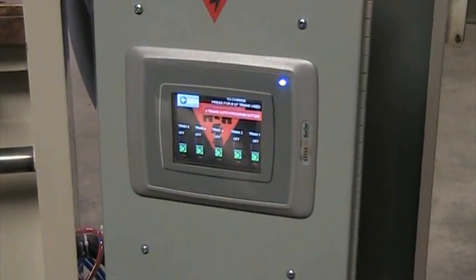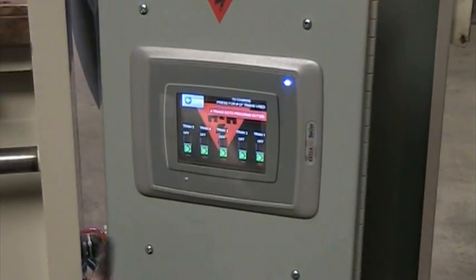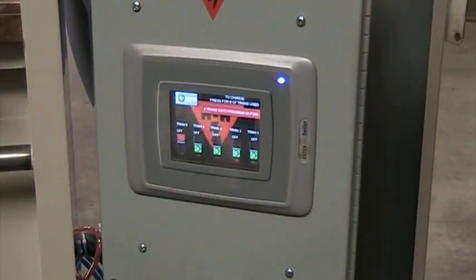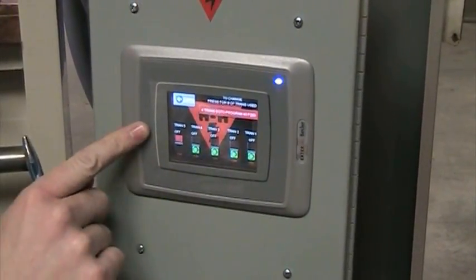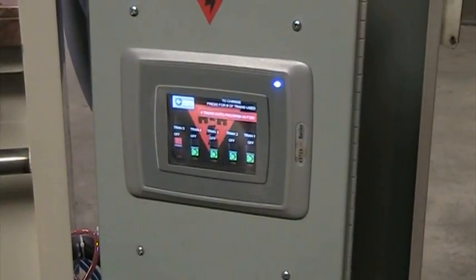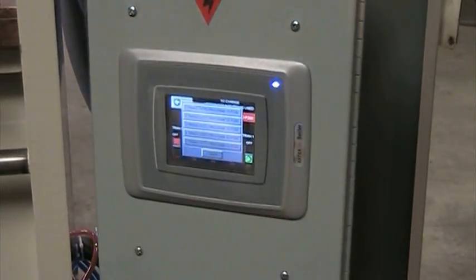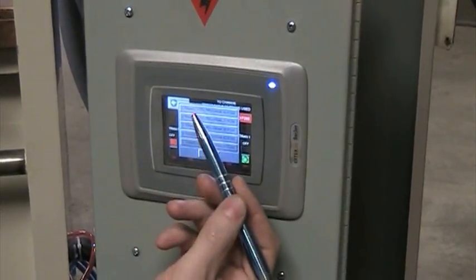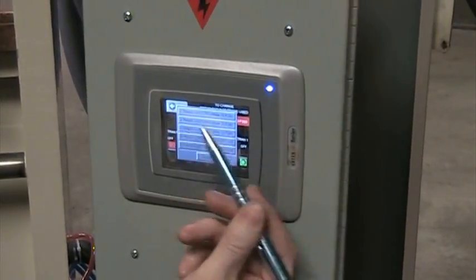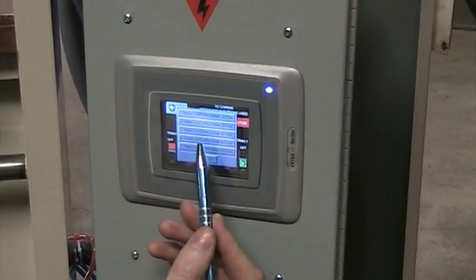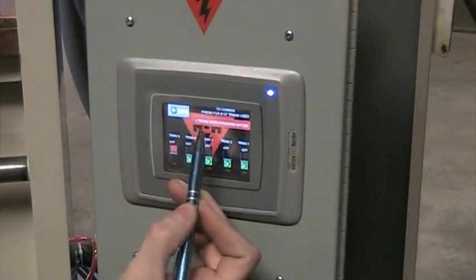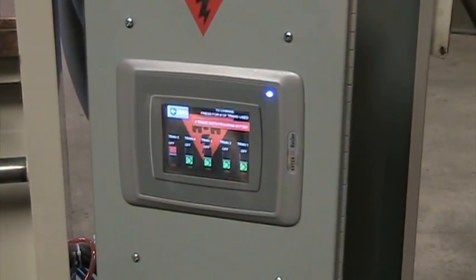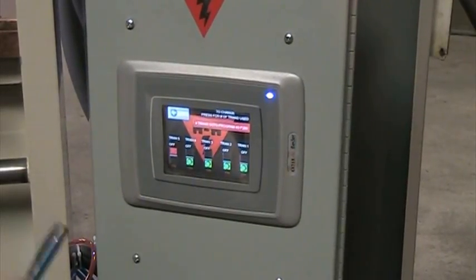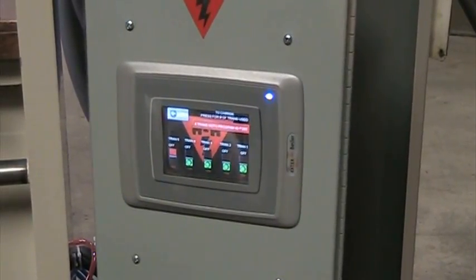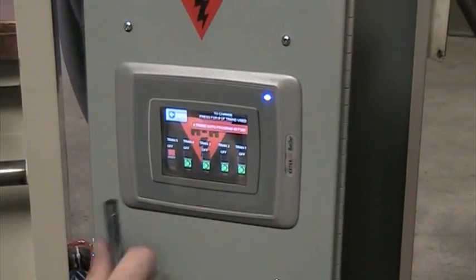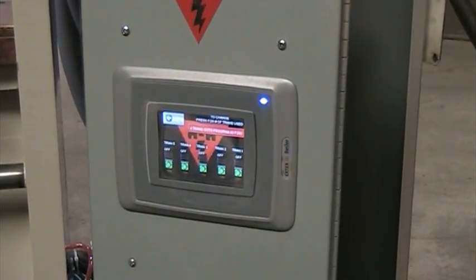If for instance you're welding on a part that requires only 4 transformers or 16 guns, you can just hit the switch, it goes to the off position, the green goes dark and the red comes on, and then select up here at the top, and you'll notice for one transformer, go to program 10, 2 transformer 20. We're going to select number 4, which tells us 4 transformers. Go to program 40 on the P280, which I'll show you in a moment, and change that, and then you're ready to start welding.